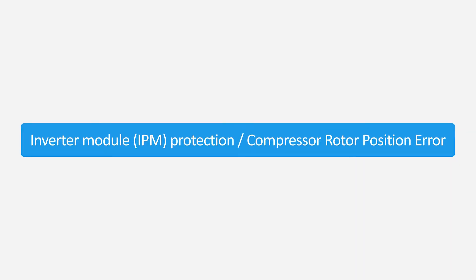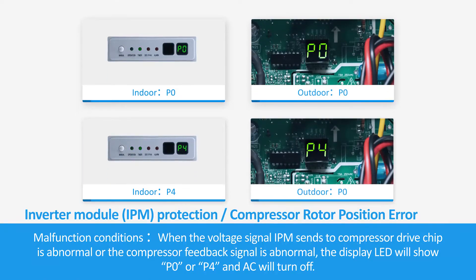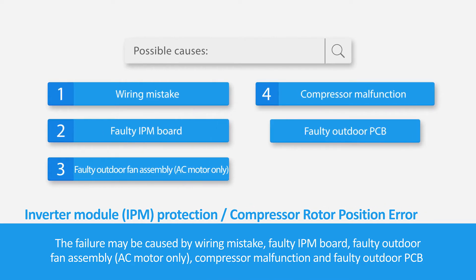Inverter Module IPM Protection — Compressor Rotor Position Error. Malfunction Conditions: When the voltage signal IPM sends to the compressor drive chip is abnormal, or the compressor feedback signal is abnormal, the display LED will show P0 or P4 and the AC will turn off. The failure may be caused by wiring mistake, faulty IPM board, faulty outdoor fan assembly, AC motor only, compressor malfunction, or faulty outdoor PCB.